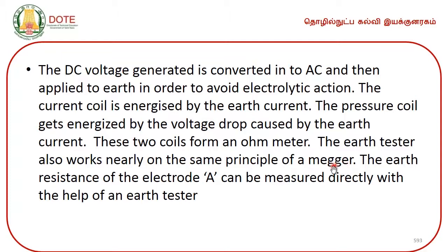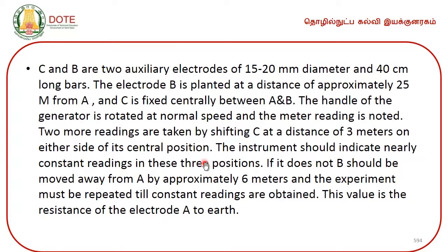The earth resistance of the electrode A can be measured directly with the help of an earth tester. C and B are two auxiliary electrodes of 15 to 20 millimeter diameter and 40 centimeter long bars. The electrode B is planted at a distance of approximately 25 meters from A, and C is fixed centrally between A and B. The handle of the generator is rotated at normal speed and the meter reading is noted. Two more readings are taken by shifting C at a distance of 3 meters on either side of its central position. The instrument should indicate nearly constant readings in these 3 positions.